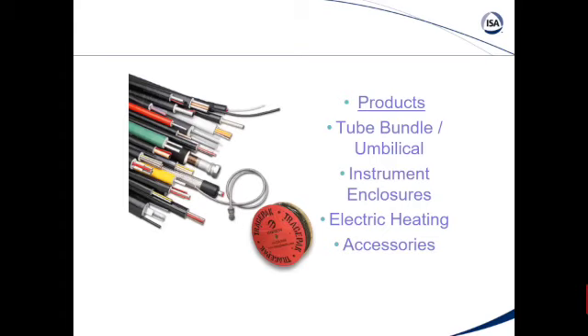Last thing I'll talk about here is tube bundle. Very quickly, when it comes to tubing, people have a misconception that installing heat tracing on large bore piping can be more difficult than small bore, when it's actually the opposite. Applying your heat tracing out in the field and properly insulating and sealing that up is much more difficult on small bore tubing than it is on large bore. Large bore, it's easy to get your hands around it. There's plenty of space to put that cable, there's an easy way to tape it. The bends aren't as tight, so you can get good contact around corners. When you have small bore tubing, you're always trying to get good contact with that heating cable, and it's very difficult. The bends are tight. There's not a lot of space. Sometimes the actual heating cable is larger than the actual tube you're tracing. It can be very difficult.